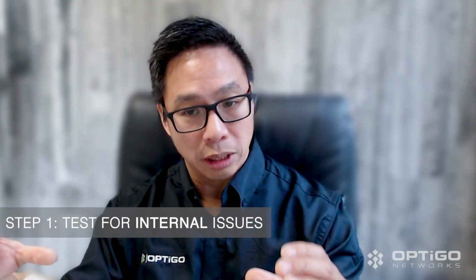The fact that an MSTP network is slow doesn't necessarily mean that it is the root cause. The root cause can come from outside. So let me ask you first, if you do have an MSTP network that is not performing well, if you disconnect it from other networks, does it continue to perform poorly?